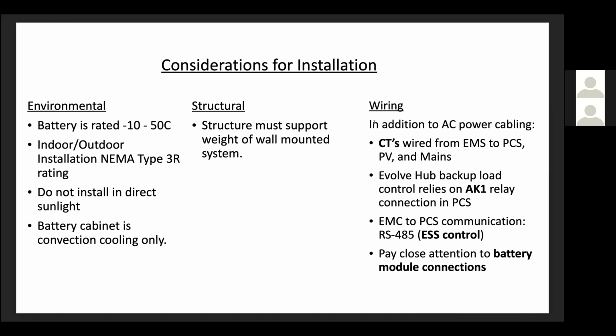So in order to minimize the cost of all of your materials, as well as the time to install it, locating the system as close to the main service panel whenever possible, whether it's on the same wall or on an opposing wall inside a garage, is usually your best bet for best practices and efficient install.